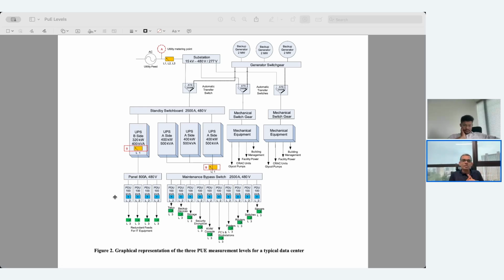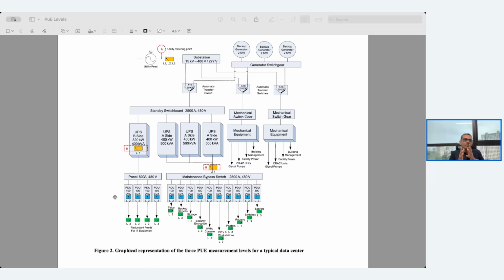At the L2, you're going at least at a daily or, if not, a weekly, once a week measurement at the PDU output. But the condition which should be adhered to is to ensure that you measure at the same time of the day, every day, if you're doing a daily measurement, or on the same day of the week if you're measuring on a weekly basis, to have a comparison with respect to PUE.